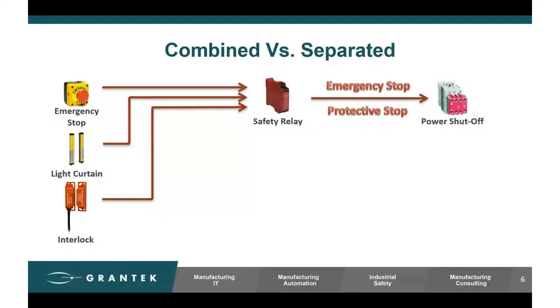So now let's separate out the functions: an emergency stop function and a protective stop function. Visually here, I chose to replace the safety relay with a safety PLC for simplicity, but this can be done with just a couple of safety relays.